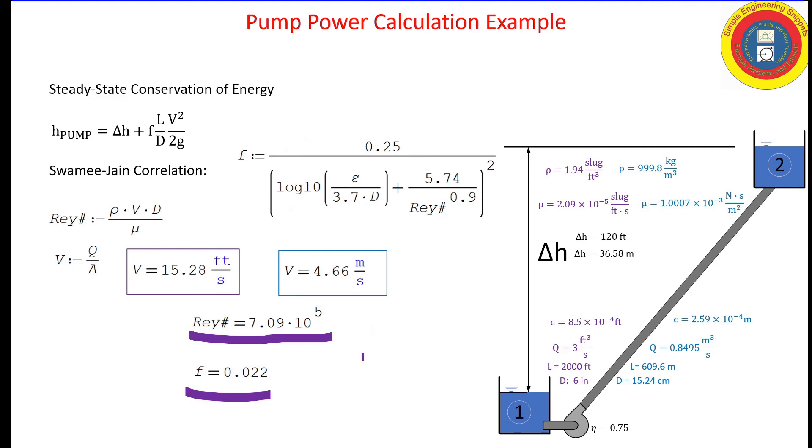Plugging all those values into the Swamee-Jain correlation, we get friction factor is equal to 0.022. That is a realistic friction factor. If it came out to be 0.2, I think that would be too high. 0.002 would be too low. So this does pass the sanity check.